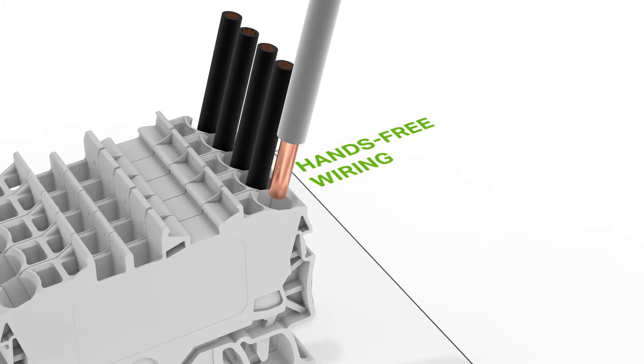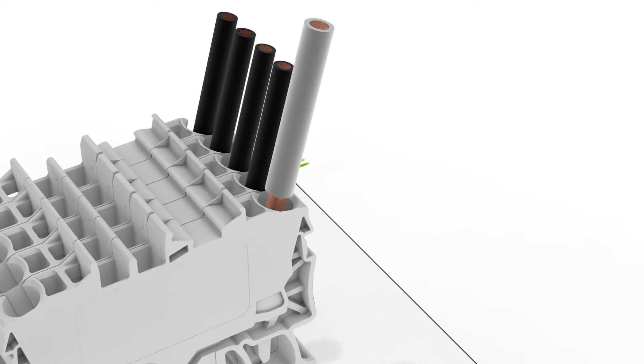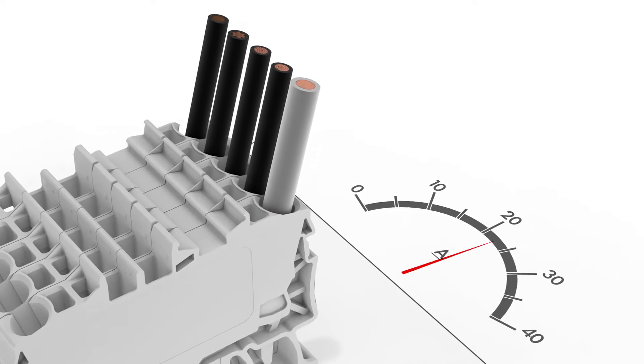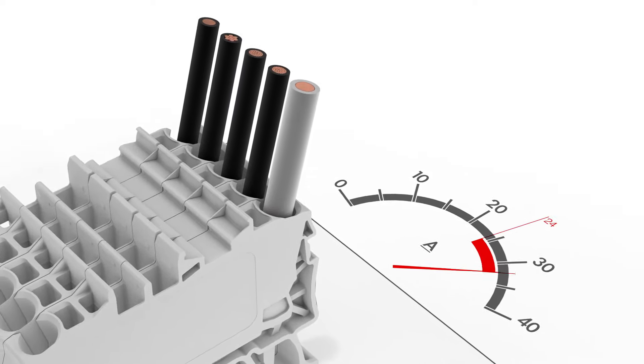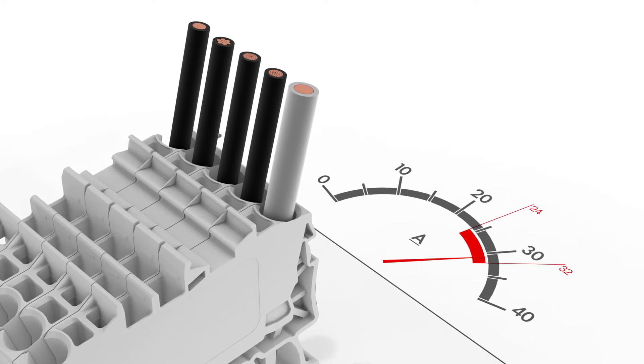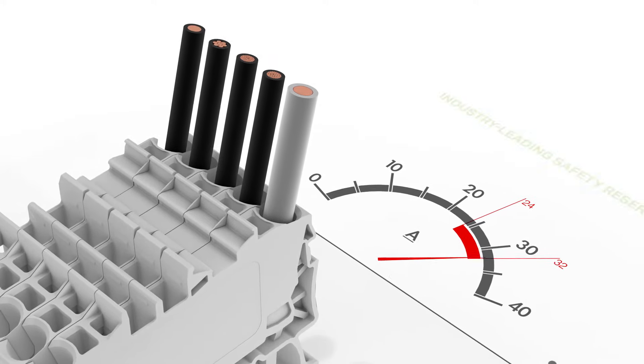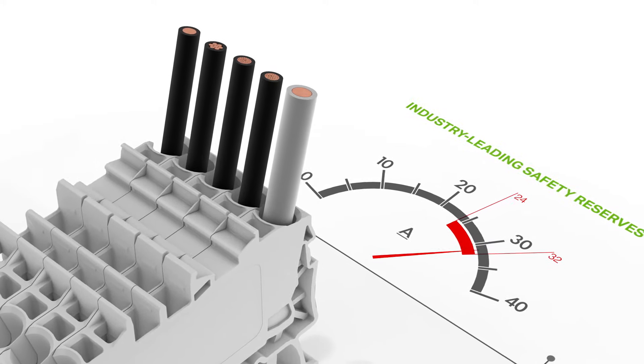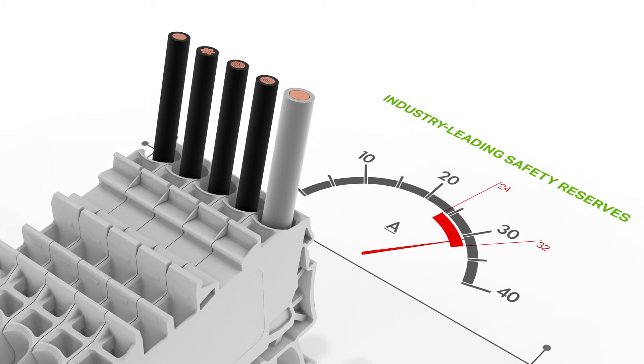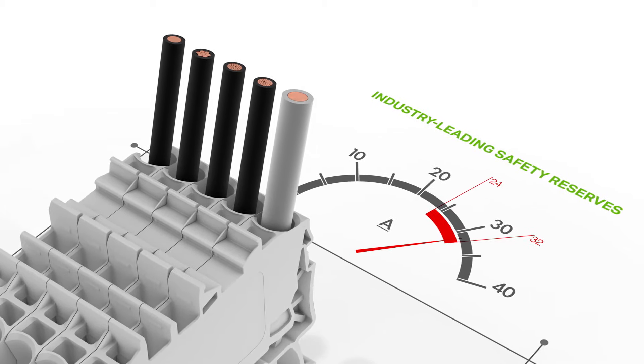All single-deck Top Job S-Rail Mounted Terminal Blocks connect unprepared conductors one size over their rated cross section and can be loaded with the nominal current of these conductors.